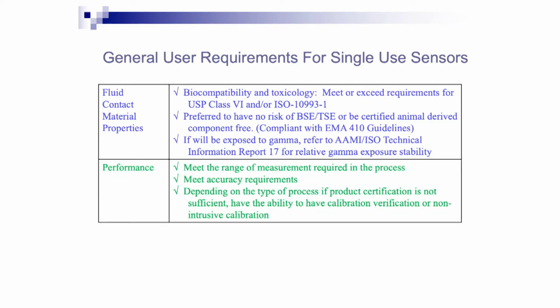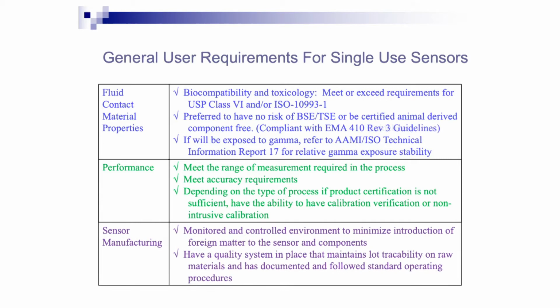In terms of performance, you have to make sure a sensor meets your requirements in terms of range, accuracy, etc. And that could also be during a preparation step where it may be exposed to higher pressures or higher temperatures. Sensor manufacturing environment, this would apply to really any single-use component, must be a controlled environment with a quality system in place.